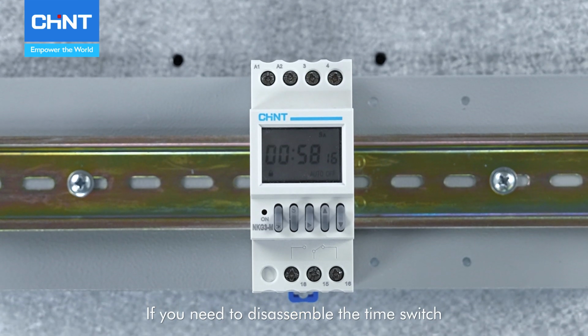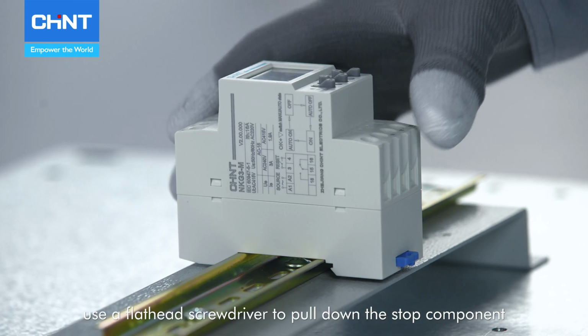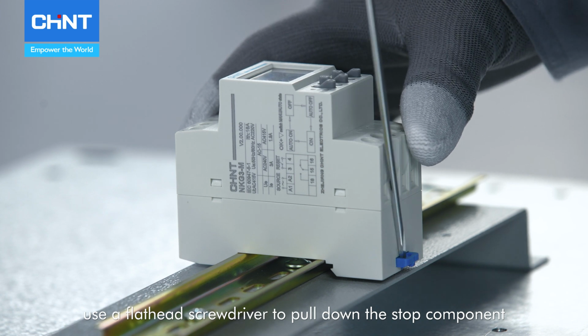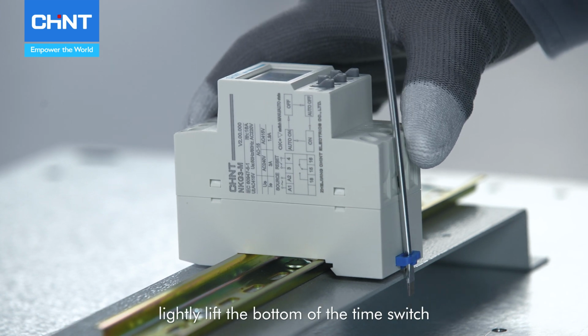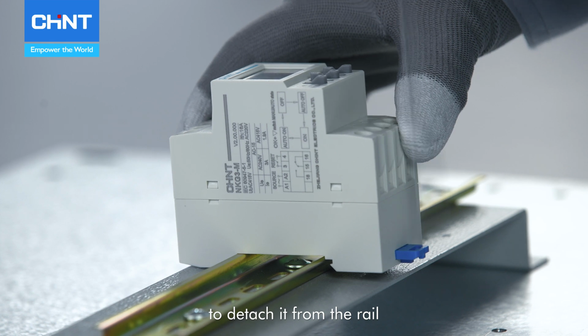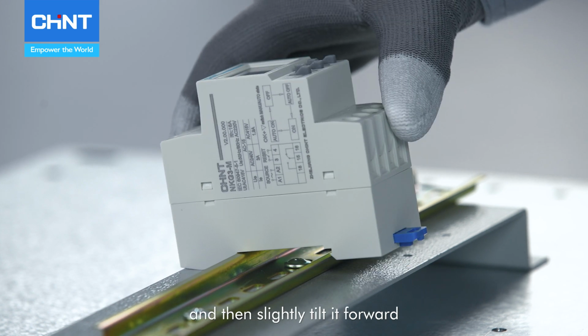If you need to disassemble the time switch, use a flathead screwdriver to pull down the stop component. Lightly lift the bottom of the time switch to detach it from the rail, and then slightly tilt it forward at an appropriate angle for smooth removal.